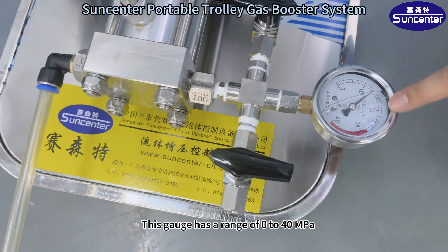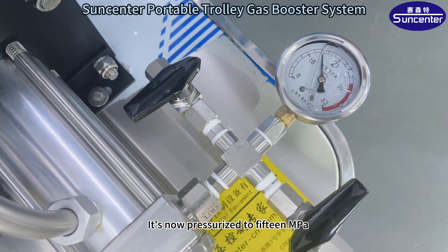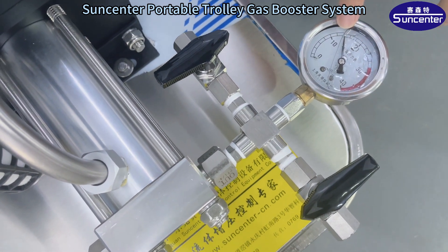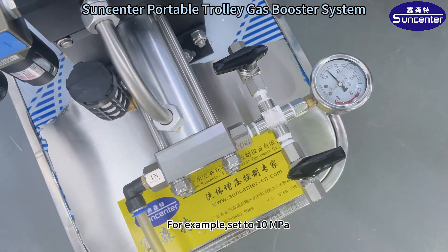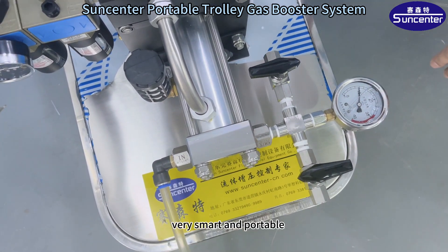This gauge has a range of 0 to 40 MPa. It's now pressurized to 15 MPa. Output pressure can be adjusted as required. Turn on the loading switch — for example, set to 10 MPa. It will automatically stop when it reaches 10 MPa.